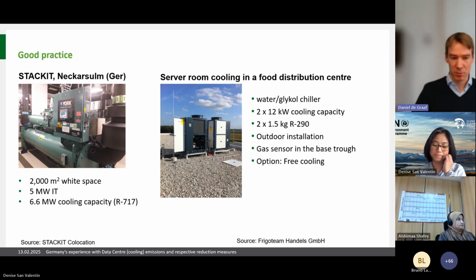On my last slide, I brought two examples where a big and a smaller data center are cooled with natural refrigerants. One is in the south of Germany, Neckarsulm, with an area of 2,000 square meters of white space, 5 megawatts of IT, and a cooling system of 6.6 megawatts. The refrigerant is ammonia in this case.